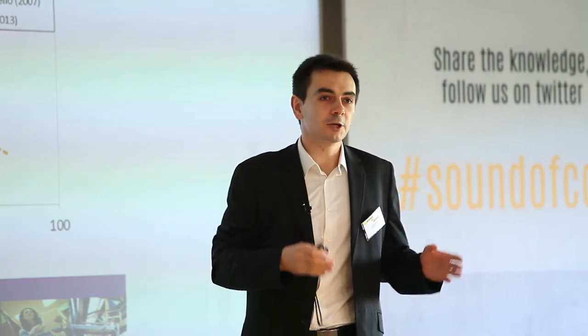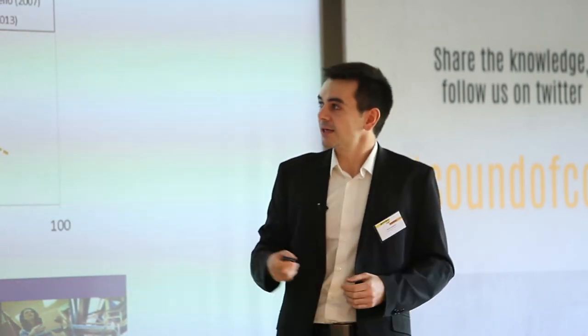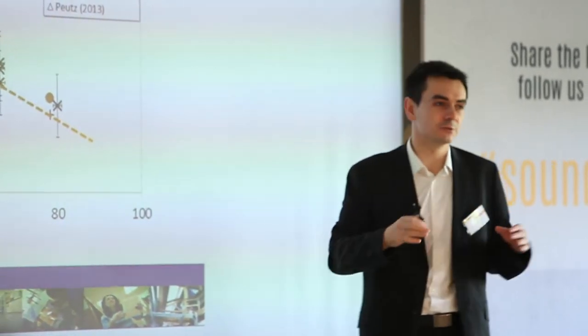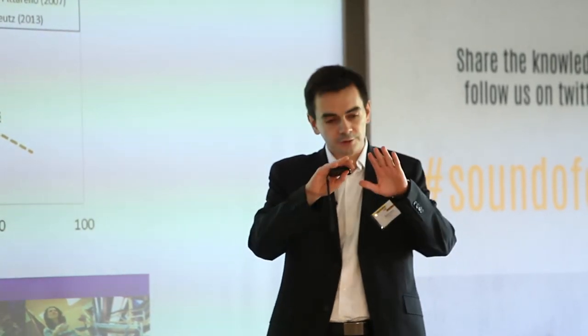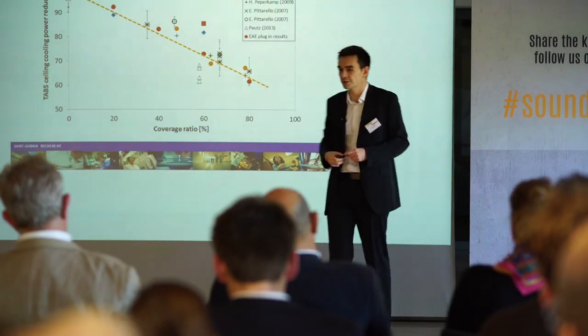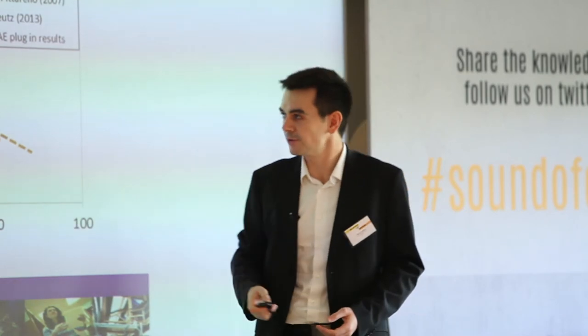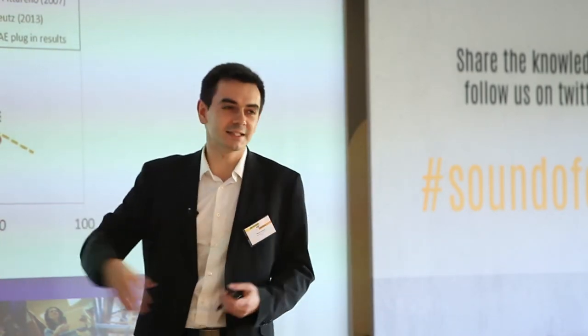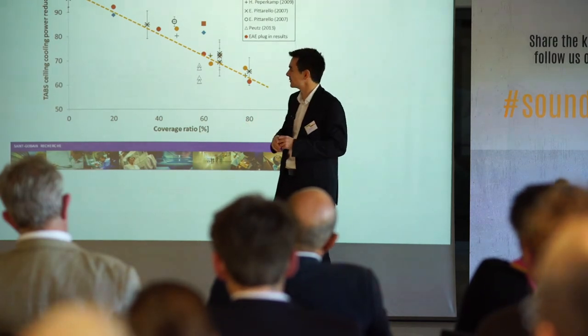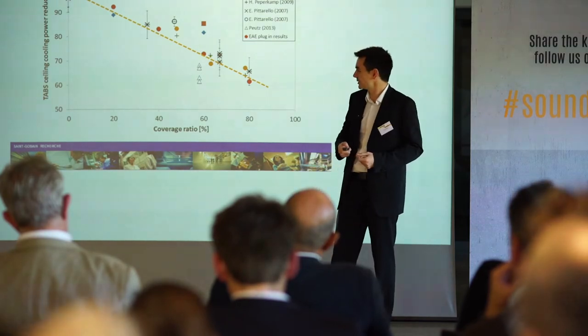Making a model is good; making a model that is correct with reality is better. So it's important to validate this. To validate, I took my previous graph — the same as before with the data — and I tried to represent a very simple case using my model with a small room, varying the ceiling coverage ratio. The results are shown as red points, which are modeling results. We can see a good correlation between the experiments and the model, which we are very happy about. But it's also a very general view, as the graph contains data from all layouts, all cases, and all distances to the ceiling. This model allows prediction of the overall behavior of acoustic panels on thermal comfort and TABS cooling efficiency.